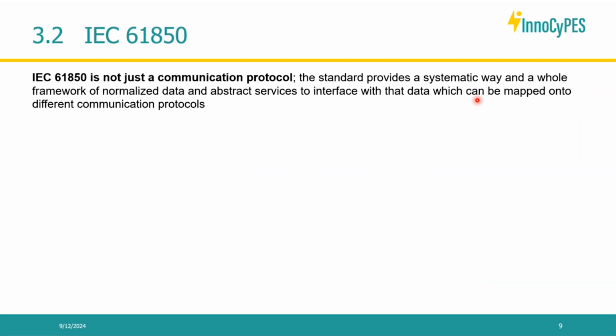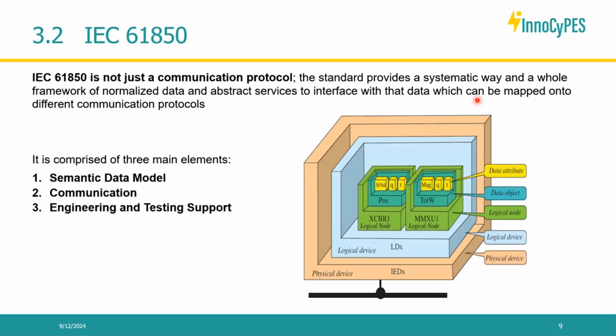IEC 61850 is an international standard by IEC, and it is not only a communication protocol, which some people confuse it for. It provides a systematic way of defining what data we need to send and how we can send it. It provides a data model that defines this data, which can be a description of instruments found in a substation.